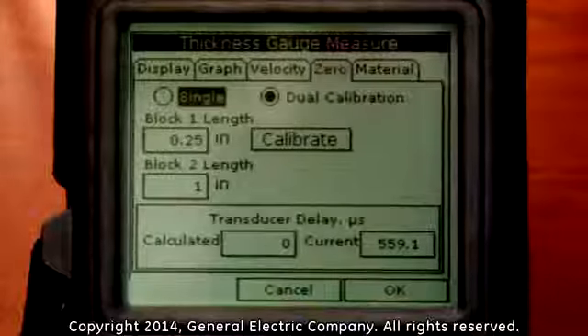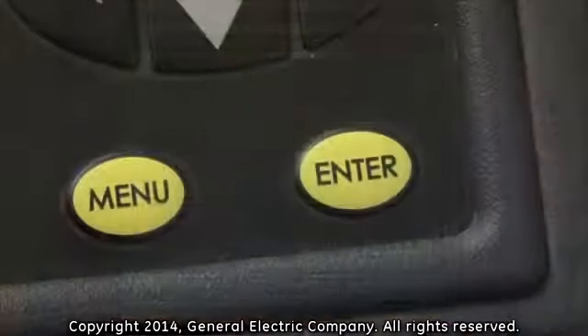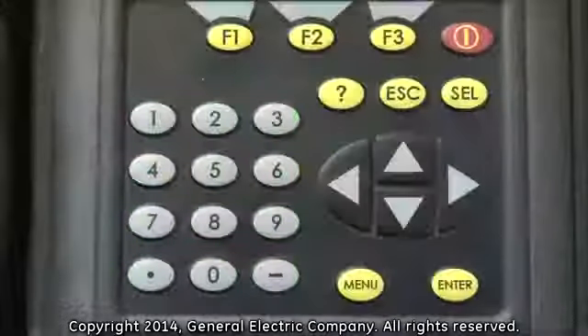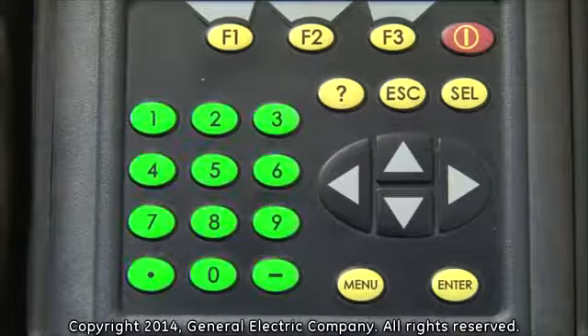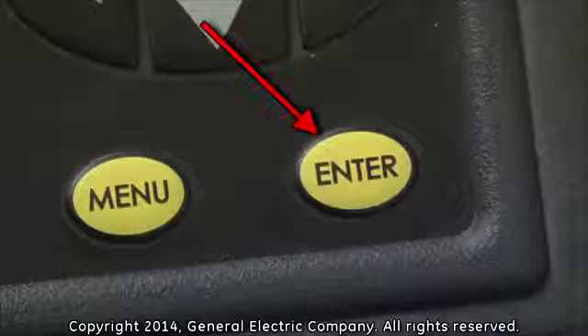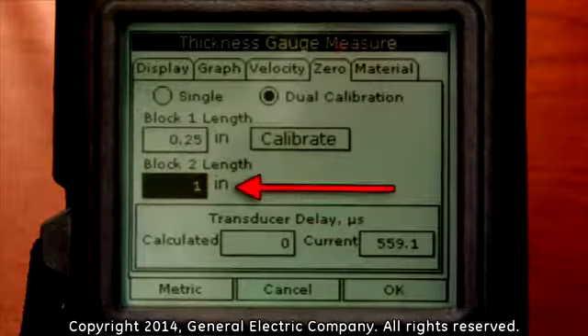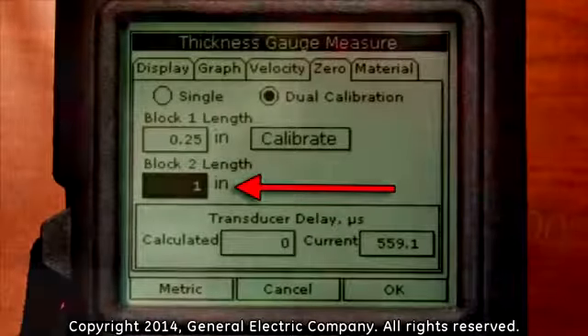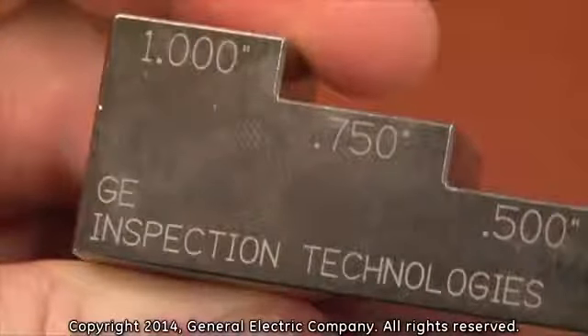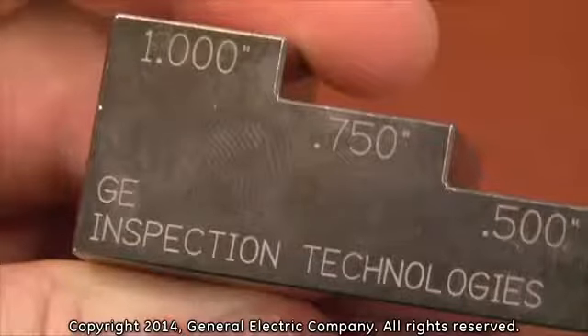If you need to change the value for the block 1 length, you would press the Enter button and use the number keys on the keypad to change the value, then press Enter to set the value. For the block 2 length, we will use 1 inch for the value. If you need to change that value according to the thickness on your test block, follow the same steps that were taken to change the block 1 length value.